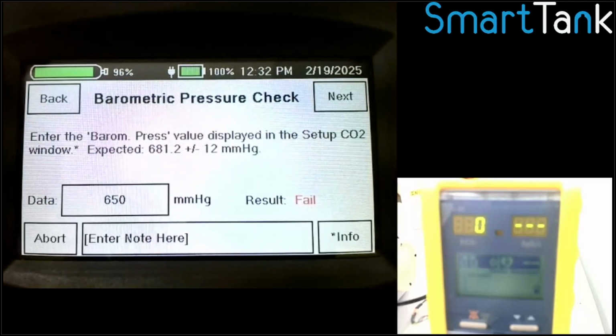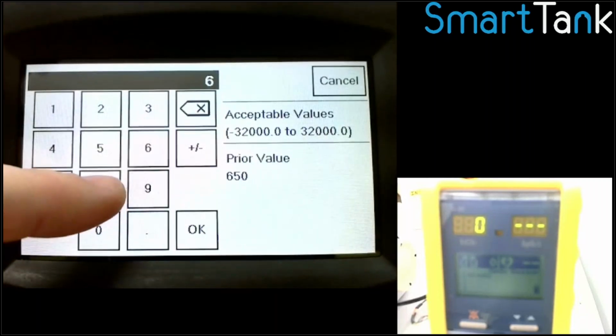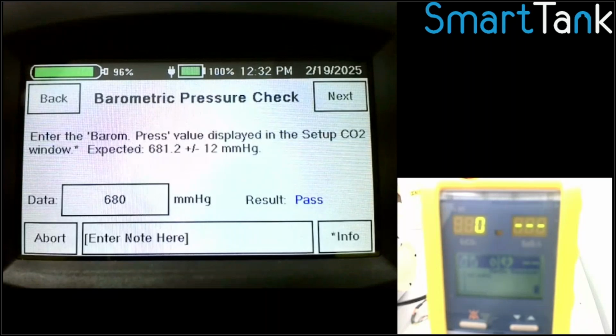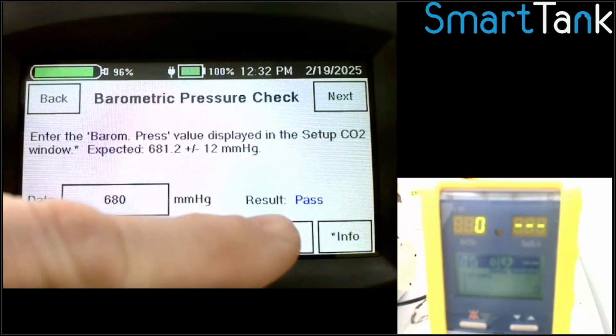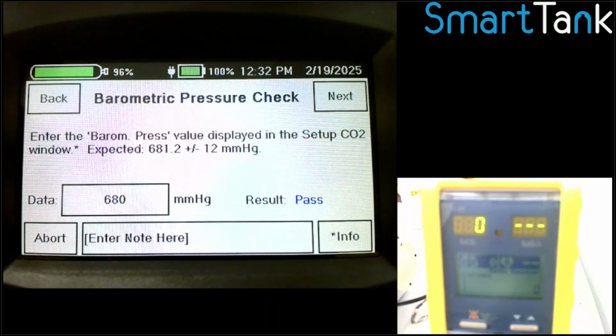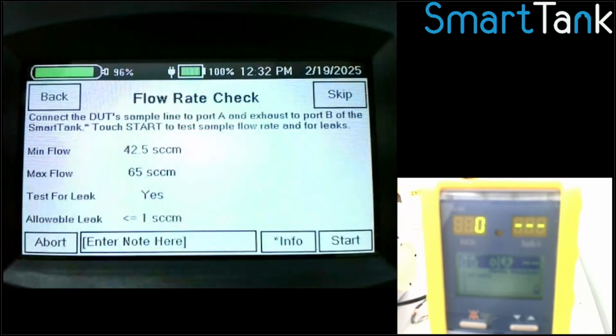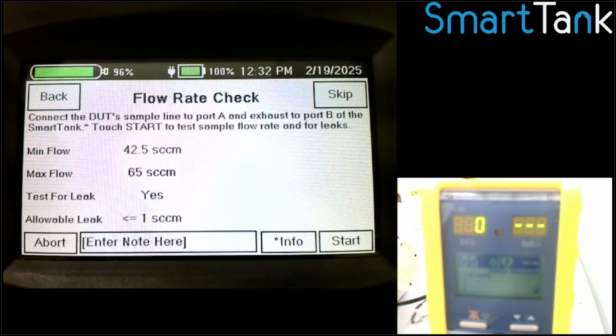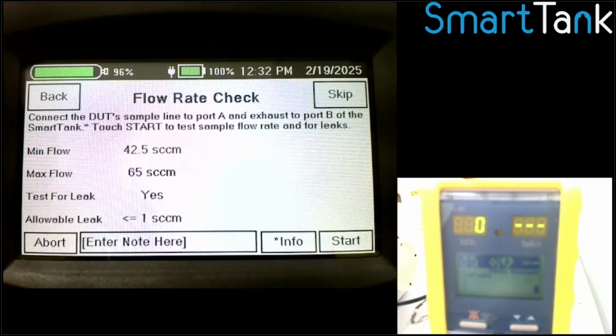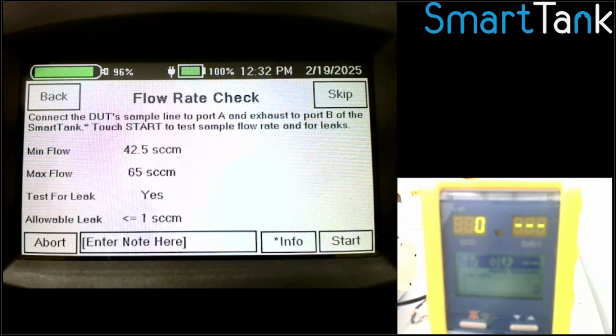So if I go back and I pass this test, let's say I put in 680. Now I've passed the test. Basically, it's in spec, and I hit next. The sequence knows that you passed that, and it will just skip the steps that you don't need to do. So again, the goal of the SmartTank is to make your PMs as fast and as efficient as possible. And so you'll be able to just skip through all that stuff. You don't have to go through and say skip or next. It just knows, and it'll just move on.